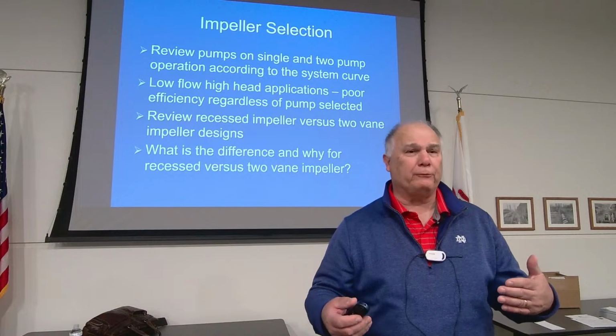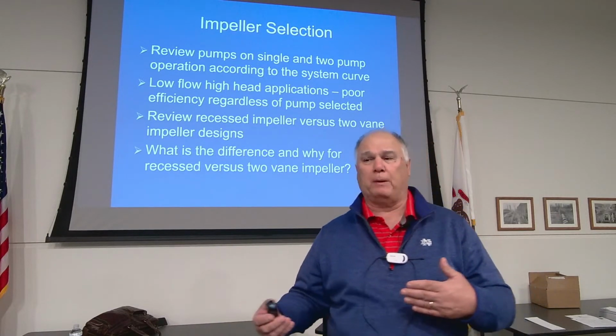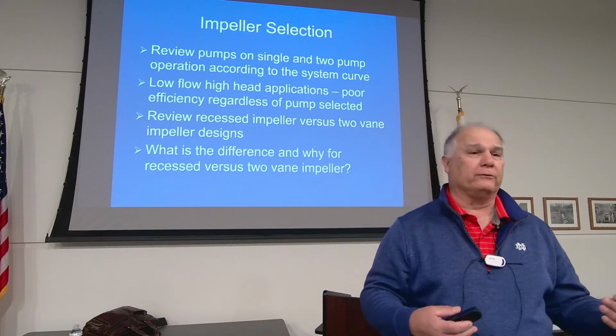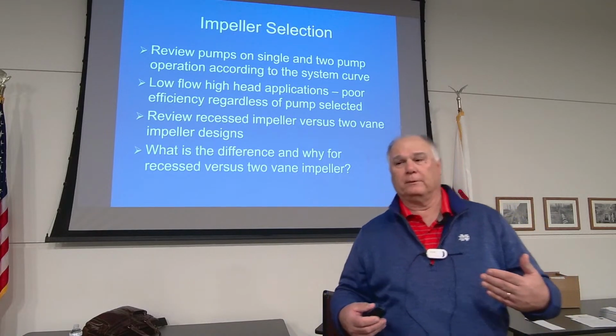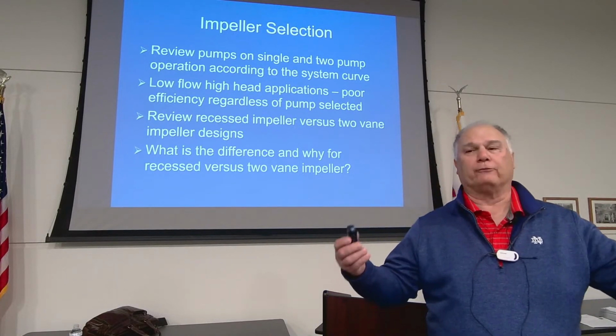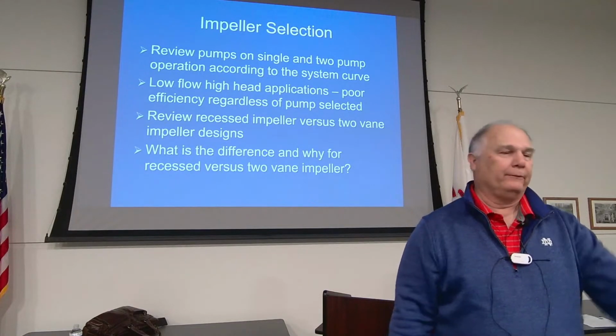I got 350 foot of TDH on this pump at 15 million gallons a day for these pumps. Needless to say, we're talking about 2,000 horsepower, something like that. Some stupid number.